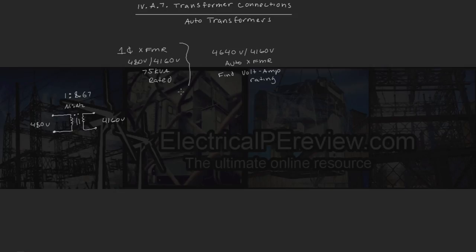Now, the most important thing we're being asked is find the volt amp rating of this new autotransformer given the information here. So the first thing we need to figure out is which winding do we need to stack on top in order to regulate 4640 volts down to 4160 volts. Well, if we subtract 4160 from 4640, we end up with 480. So that tells us that we need to stack our primary winding on top of our secondary winding. Let's see if the math checks out.